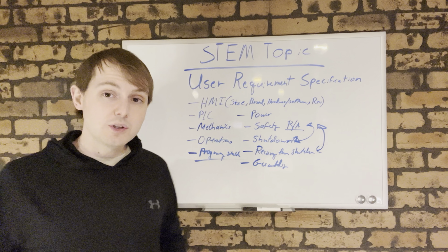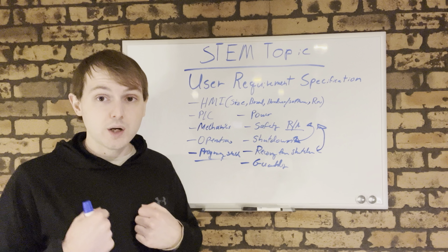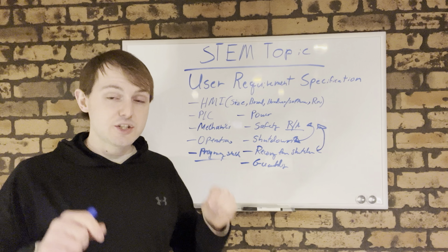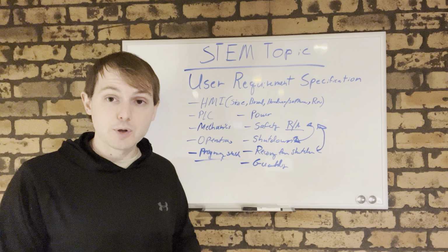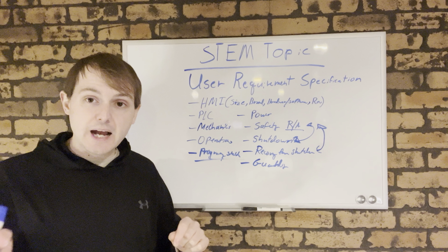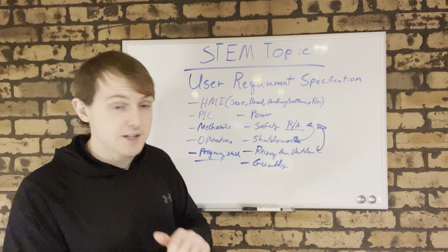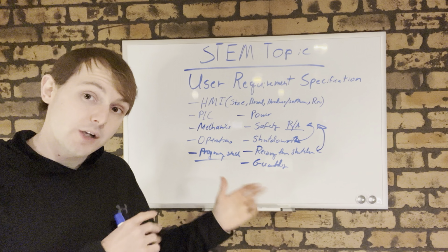You're not allowed to use a latching. That's one I've actually seen a lot of. And in fact, I really hold on to that dearly too, is that latching should be very, very limited within your program, of a PLC program, that is. So a latch on, latch off, and it should be within 5 rungs of each other. So just kind of a heads up there on that. So something along the lines of programming.